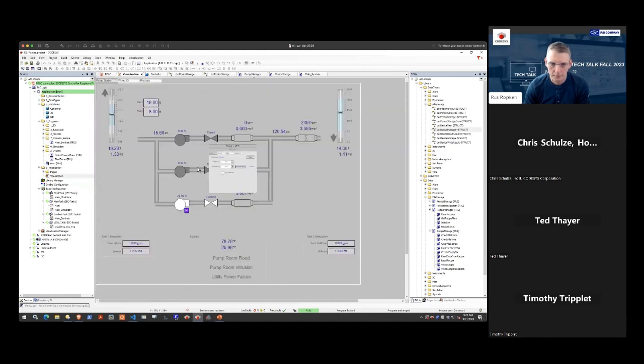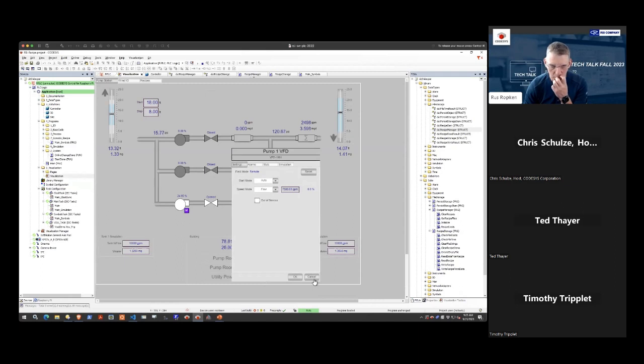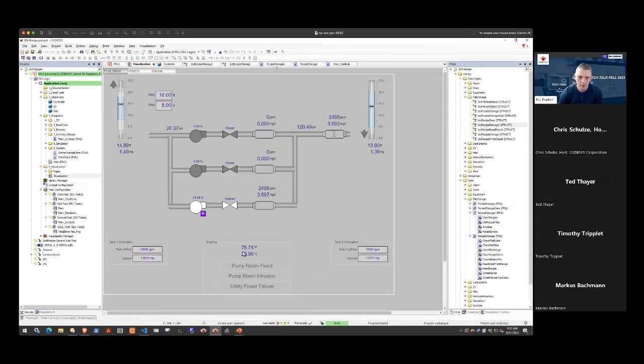Now, before we push this in, let's take a look at pump 1. Its current flow set point is 7,500. And why don't we just get these things running real quick so we can see it changing too. So I'll just fake in my settings here and get that pump to start up. There we go. As you can see, pump 1 and 2 are starting up since they're in auto mode. And we should jump up to about 7,500.